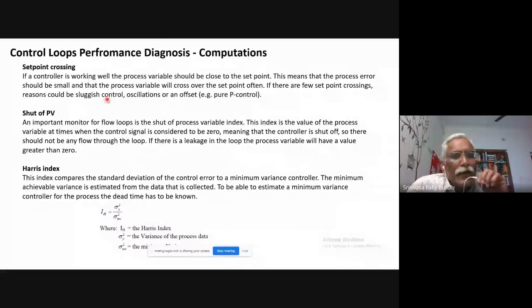So indicating that it is basically having some offset issue also. So that is how we make use of the set point crossing calculations. Then another calculation that is done is shut of PV. When the control output is 0, what is the value of the process variable? Suppose, ideally speaking, if the control valve is not leaking, when you close the control valve and the output signal is 0, there should not be any flow signal.